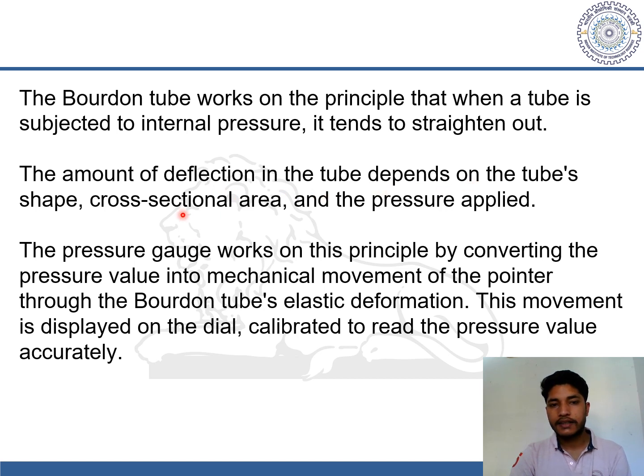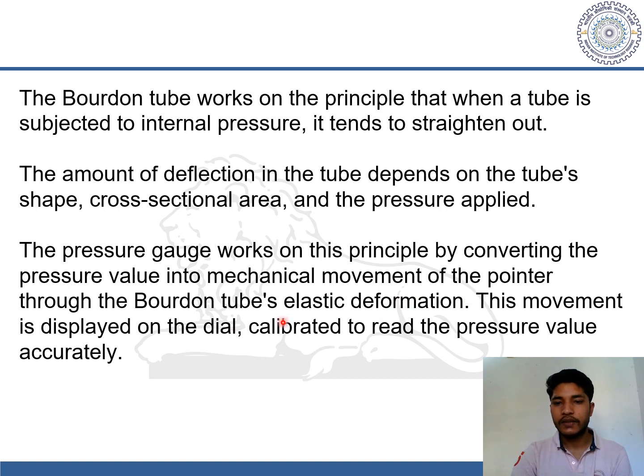The amount of deflection in the tube depends on the tube's shape, cross-sectional area, and the pressure applied. The pressure gauge works on this principle by converting the pressure value into mechanical movement of the pointer through the Bourdon tube's elastic deformation. This movement is displayed on the dial, calibrated to read the pressure value accurately.